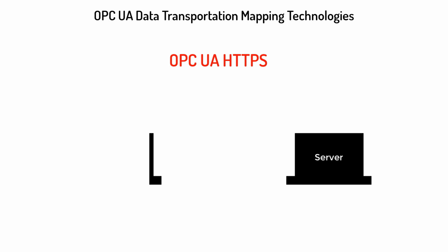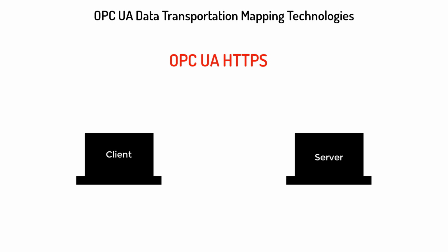Now let us take a look at OPC UA HTTPS. Now with HTTPS transport protocol, an OPC UA client and server are essentially exchanging OPC UA messages as regular HTTP messages over an SSL connection. The syntax of the HTTP messages is maintained. The only difference is that a TLS connection is created instead of a TCP IP connection. What that means is that an OPC UA Stack Profile that implements HTTPS for data transportation can also be used with HTTP when security is not an issue.